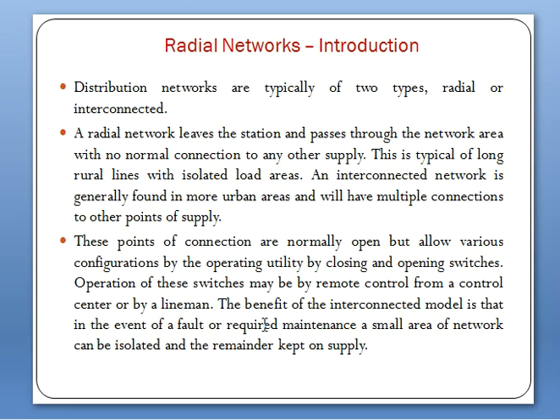Within these networks, there may be a mix of overhead line construction utilizing traditional utility poles and wires, and increasingly underground construction with cables and indoor or cabinet substations. However, underground distribution is significantly more expensive than overhead construction. In part to reduce cost, underground lines are sometimes co-located with other utility lines in what are called community ducts. Distribution feeders emanating from a substation are generally controlled by a circuit breaker, which opens when a fault is detected. Automatic circuit breakers may be installed to further segregate the feeder, thus minimizing the impact of faults.